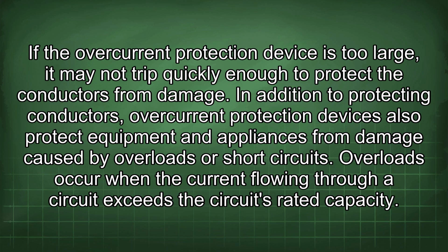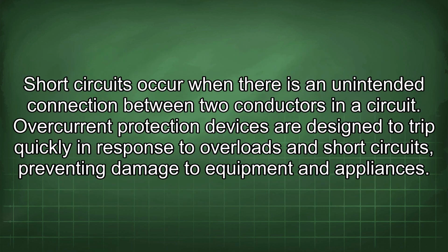from damage. In addition to protecting conductors, overcurrent protection devices also protect equipment and appliances from damage caused by overloads or short circuits. Overloads occur when the current flowing through a circuit exceeds the circuit's rated capacity. Short circuits occur when there is an unintended connection between two conductors in the circuit.